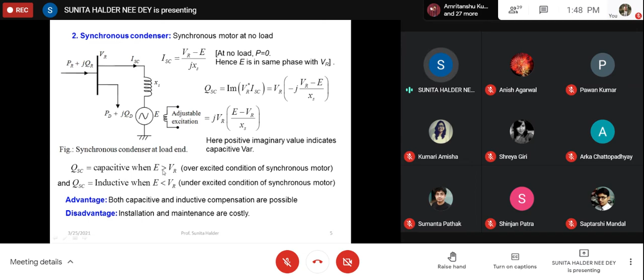Now next is the static var compensator and synchronous motor. One more thing. Now in this, you will control the excitation to make it capacitive or inductive. Obviously along with that, if there is a control circuit sensing VR, then by comparing with some preset value, this excitation control can sense whether VR is greater or less than the preset value. So depending on that it can sense whether it is an over voltage problem or an under voltage problem. Accordingly it can operate in over excited mode or under excited mode. So it may be automatic also, with the help of some power electronics interface and some control circuits.